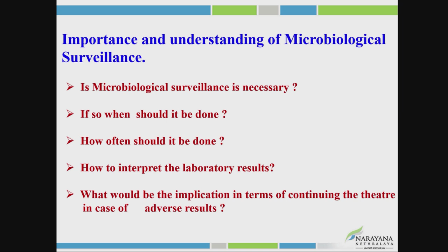Microsurveillance is done during routine surveillance monthly in designated OT areas, and when a new hospital is constructed. Once the hospital is constructed, after all the validation is done of the HEPA filters, AHU, and different protocols, we need to check the microsurveillance in all the OTs. All three cultures should be negative, then only should we go for commissioning of the OT. It's very, very important for a new hospital construction. And when there has been an outbreak of endophthalmitis, either sporadic or cluster infections.